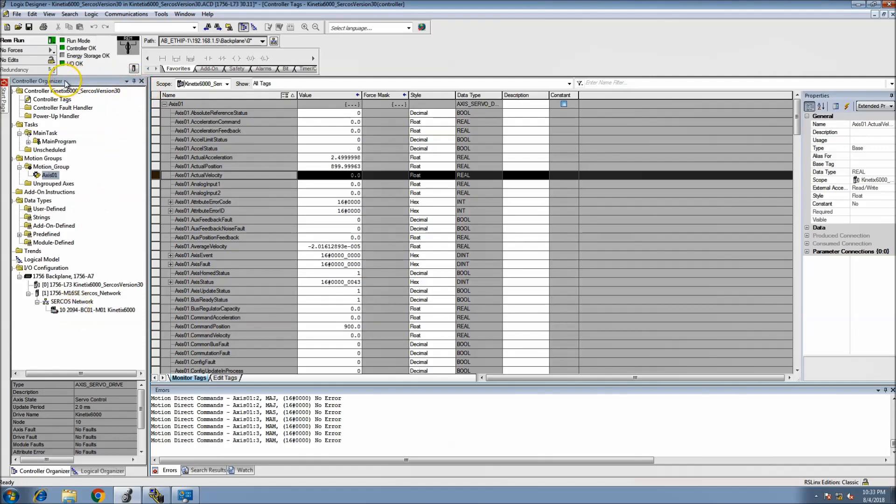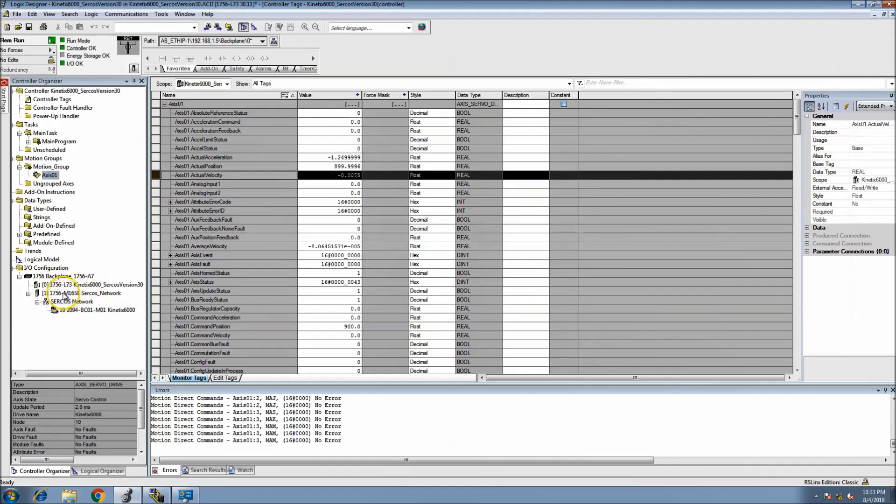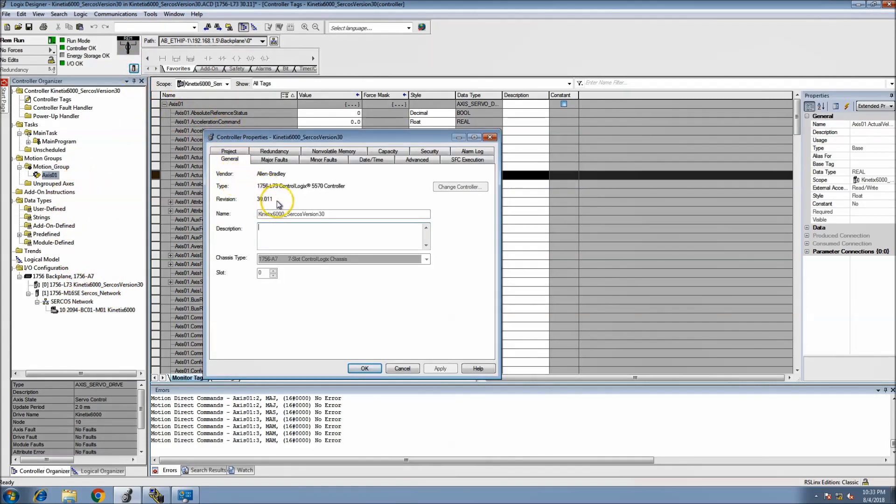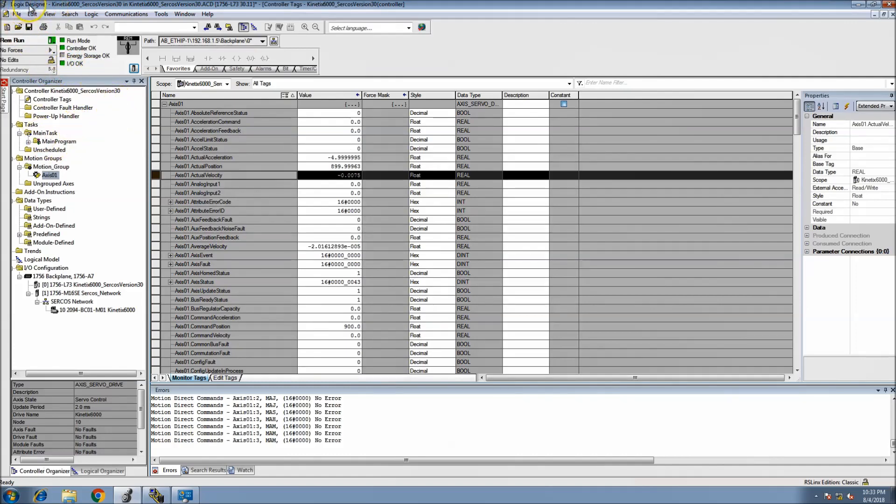But the purpose of this video is to set up a SERCOS network on Version 30, which is running an L7 processor. There has been somewhat of a talk, at least not from Rockwell but from others, saying that you can't run a SERCOS network on Version 30, and you can. That obviously shows that I am running a SERCOS network on Version 30, and this is Studio 5000, Logix Designer, which is basically Studio 5000.